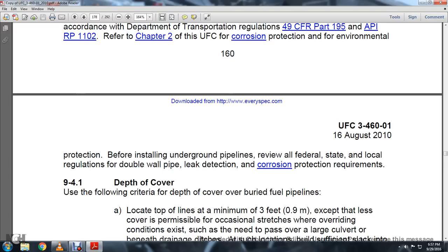Locate the top of the lines at a minimum of 3 feet of cover, except less cover is permissible for an occasional stretch with overriding conditions existing, such as the need to pass over a large culvert beneath a drainage ditch. At such locations, build sufficient slack into the line to allow vertical lateral movement down due to frost heave, and refer to the UFC 3-201 series for additional guidance.